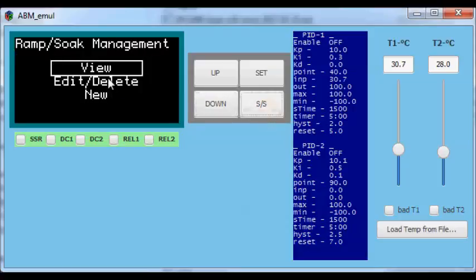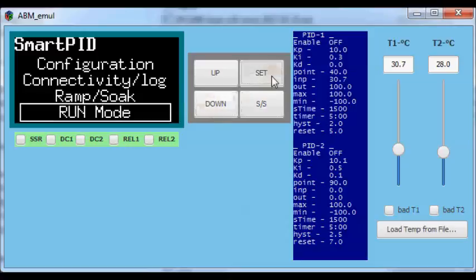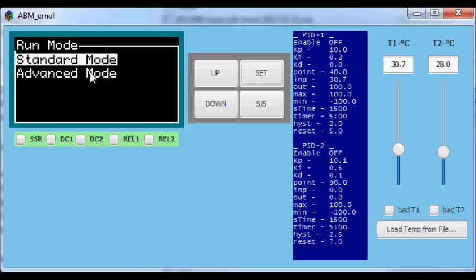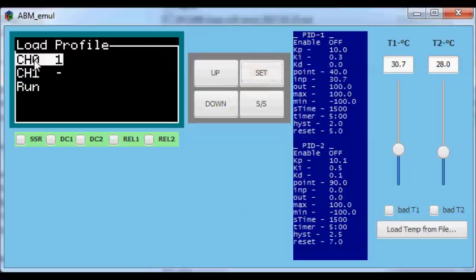Once you have defined your profile you can save it or override an existing one. Let's go back to the main menu. The run mode has been modified by adding a second-level menu. In standard mode nothing changes — you can run your controller in PID or on/off mode as usual, setting your setpoint manually. In advanced mode you are requested to load the associated profile for the channel. Remember that you have two completely independent channels, so you can assign two different profiles. Profile 1 is already defined and associated to channel zero.